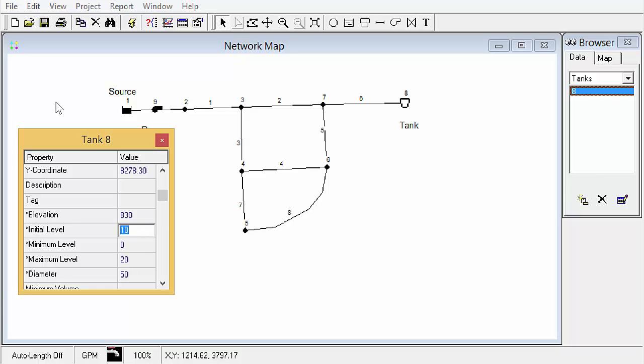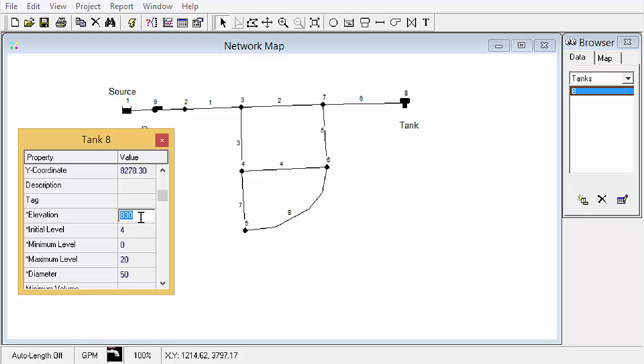So we're going to give it an initial level of 4 and all these level initial, minimum and maximum are measured above the tank base level. So this elevation, this is the base level or you could consider it the bottom of the tank. That will have some interesting ramifications when we try to model hydropneumatic tanks as a tall skinny tank or elevated storage and we'll cover that in the advanced videos. For now, we'll just keep working through this tutorial. Minimum level, we're going to leave at 0. Maximum level, 20 and a diameter of 60. And again, we're in English units so that will be in feet.